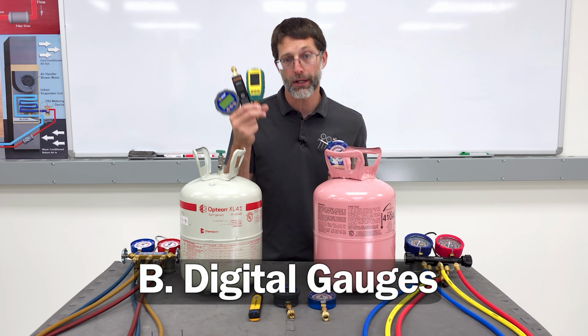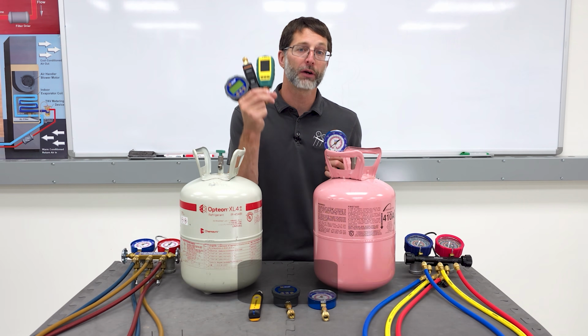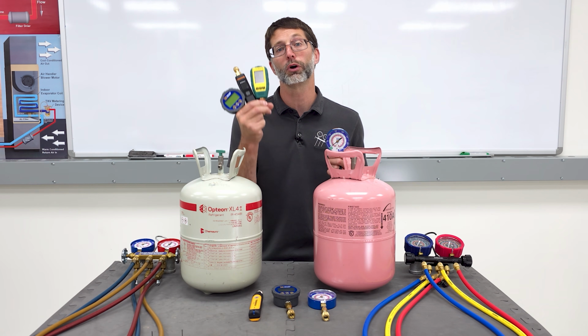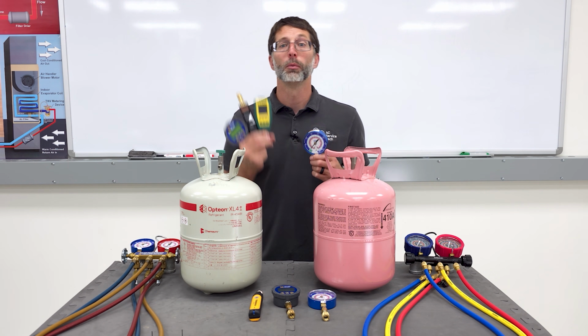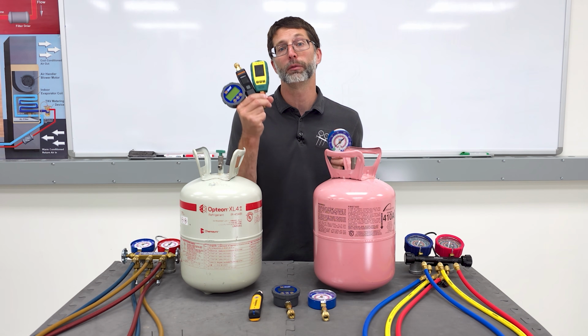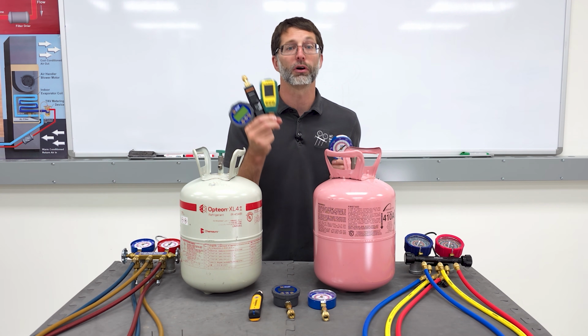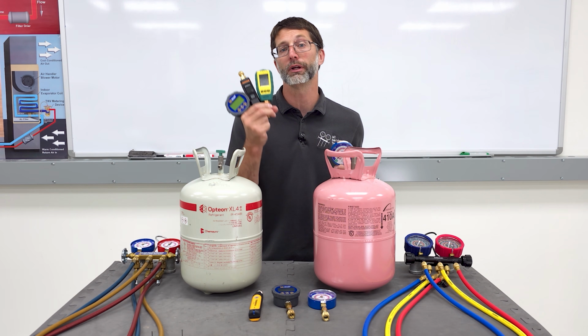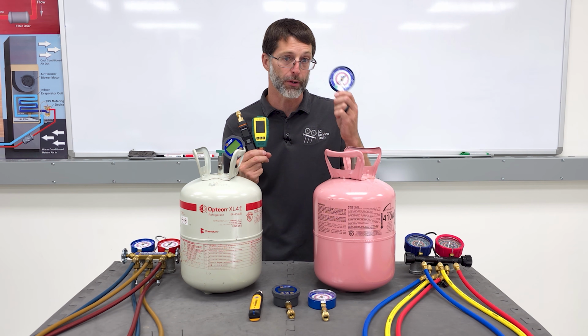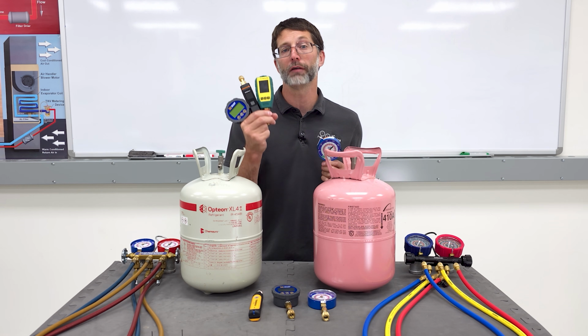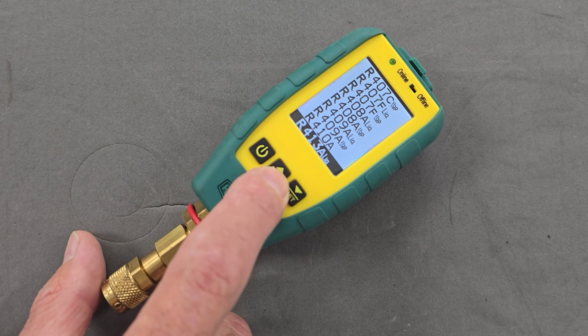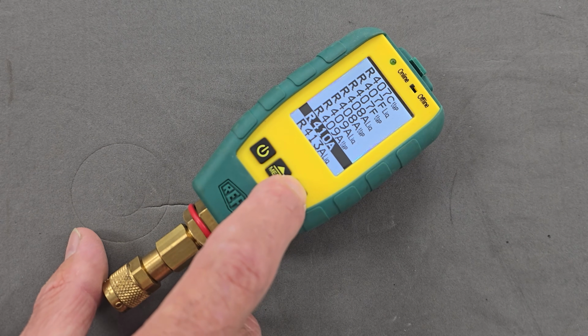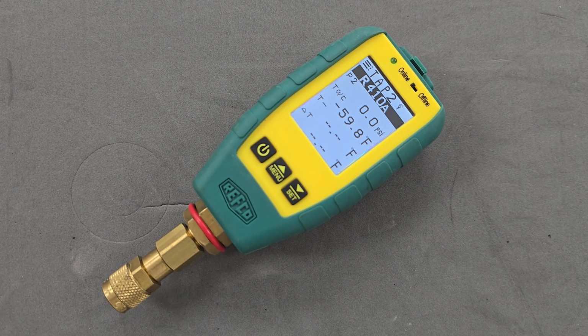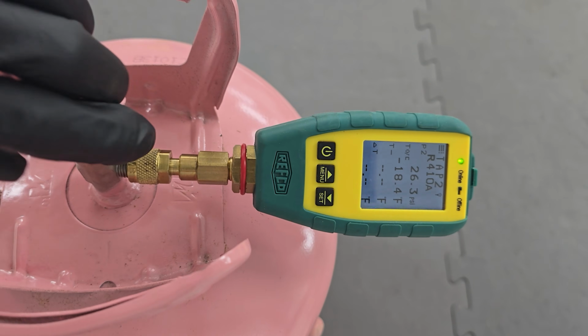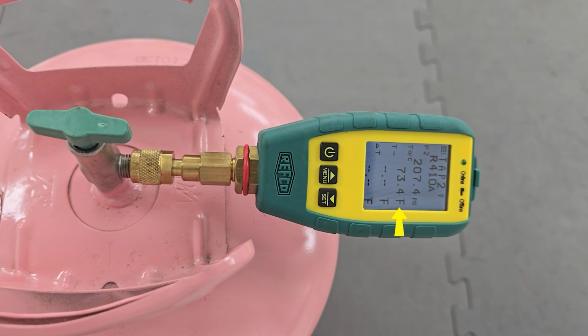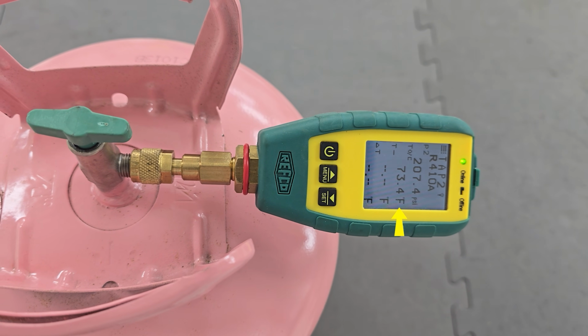Section B, digital gauges. Digital gauges have a much higher accuracy and can be read and interpreted more quickly than compound gauges. Pressure is measured in 1/10 of a psig. Digital gauges are also not limited to converting pressures to only 3 saturated temperatures like compound gauges. Digital gauges may have the saturated temperatures of up to 70 refrigerants programmed within the tool. After the refrigerant type is selected by the user, anytime pressure is measured, the saturated temperature is automatically calculated and displayed to the closest 1/10 of a degree Fahrenheit.